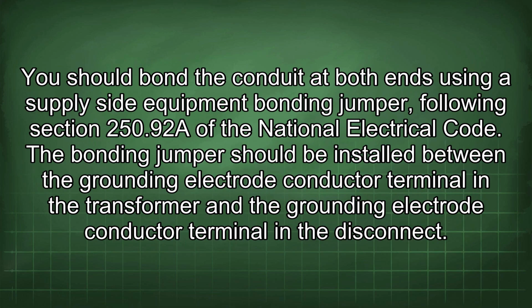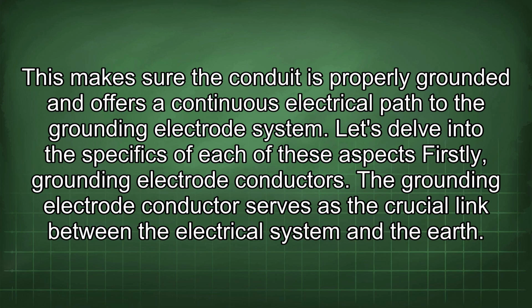You should bond the conduit at both ends using a supply-side equipment bonding jumper, following Section 250.92 of the National Electrical Code. The bonding jumper should be installed between the grounding electrode conductor terminal in the transformer and the grounding electrode conductor terminal in the disconnect. This makes sure the conduit is properly grounded and offers a continuous electrical path to the grounding electrode system. Let's delve into the specifics of each of these aspects.